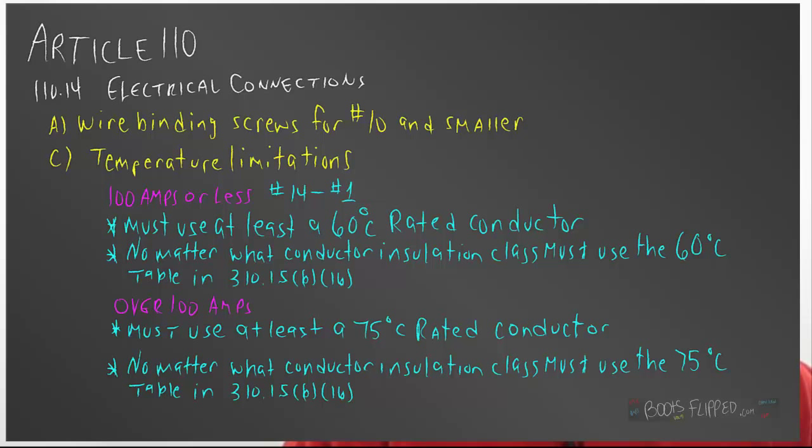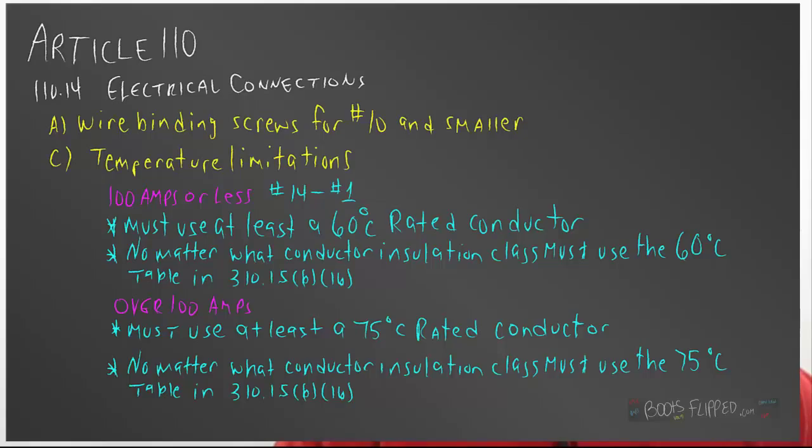Now, once we get over 100 amps, we can use the 75-degree table. Well, that at least gives us one more table over, as long as the insulation class we're using is 75 degrees or above. And let me point out that in both of those applications, if you're at 100 amps or less, you have to use wire that's rated for 60 degrees or more. And in a 100 amp or over 100 amp application, you have to use wire that's rated 75 degrees or more.